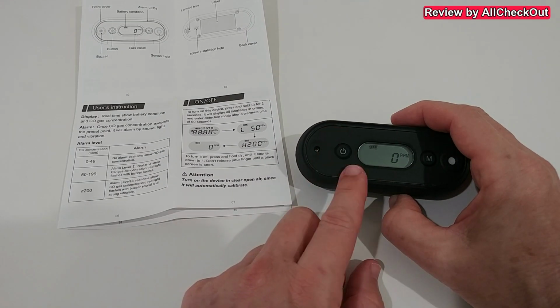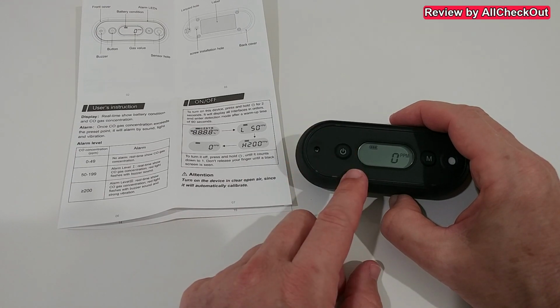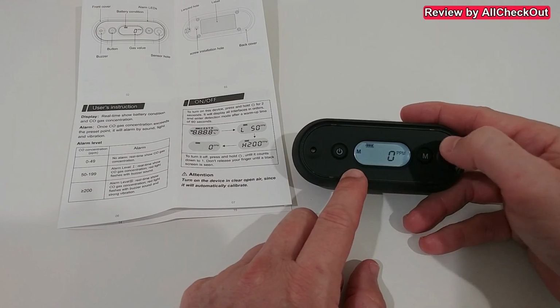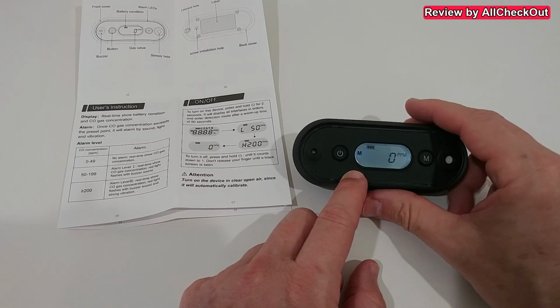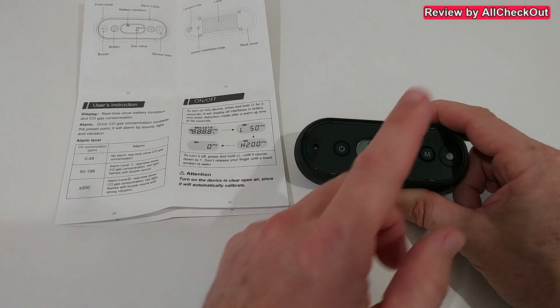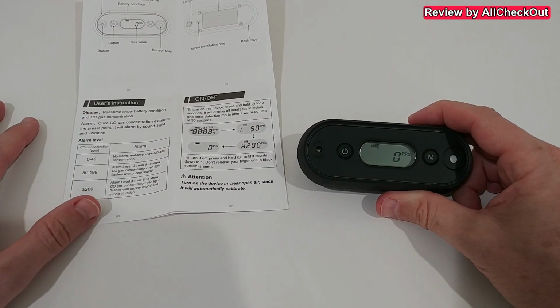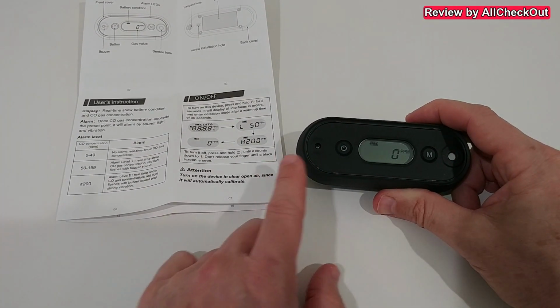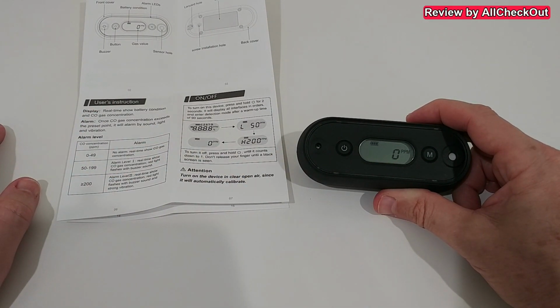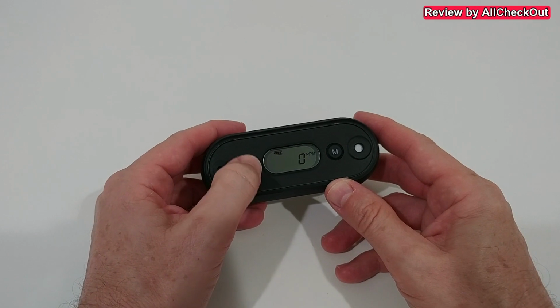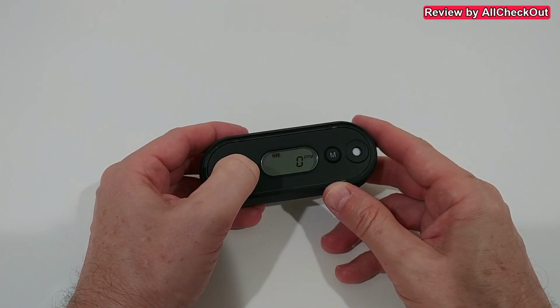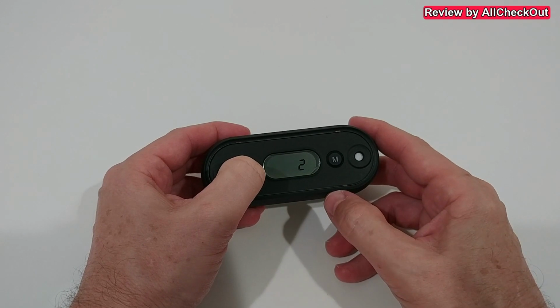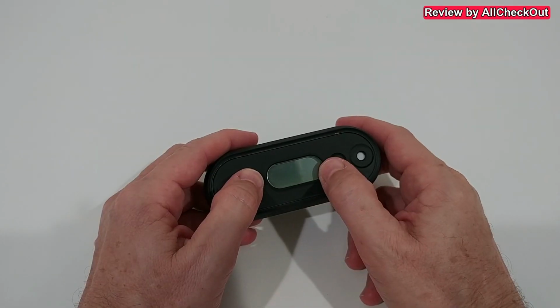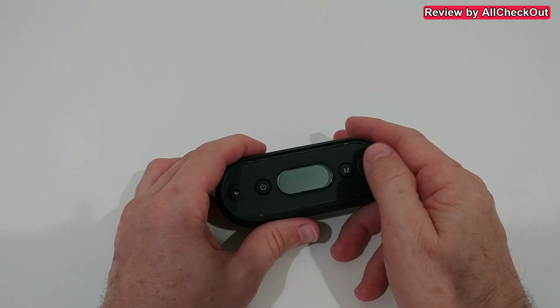The things which you have to keep in mind are, again, the battery runtime, which is around 2 years. Of course, when you're using the background illumination, it will be a little bit shorter. And the second important thing is that the life expectancy of this sensor is around 5 years. So I recommend to write down somewhere the date when you started this and replace it after around 5 years to be safe. And if you want to turn off the device for some reason, you have to hold the on-off button for a longer time. Then you can see the countdown. You have to keep holding for the whole time, and after 3 seconds it will be turned off.